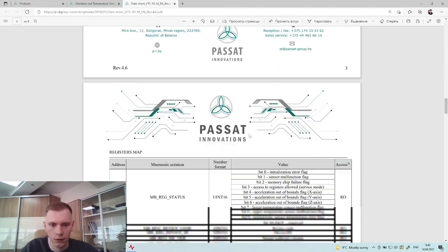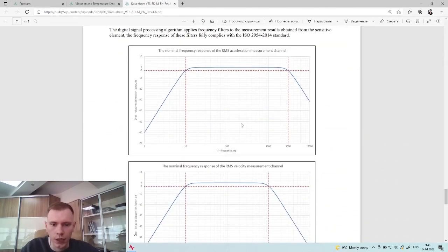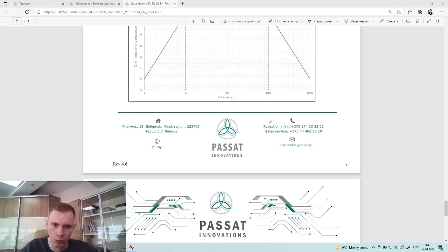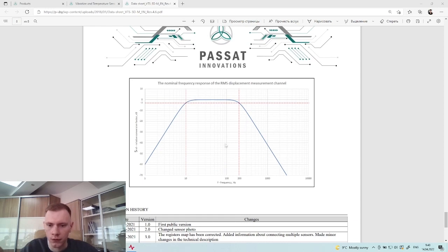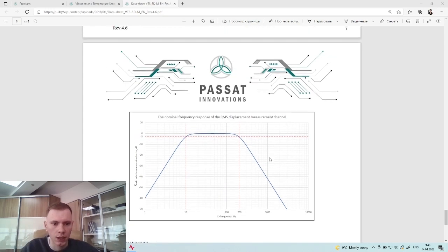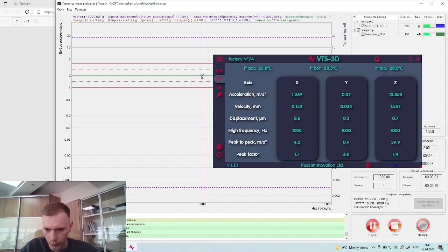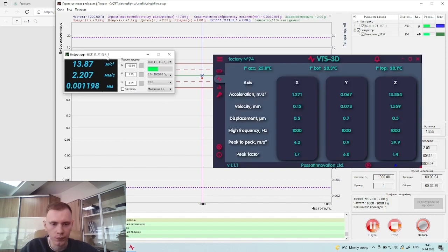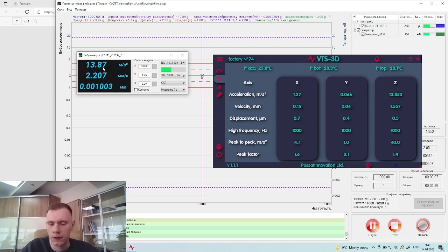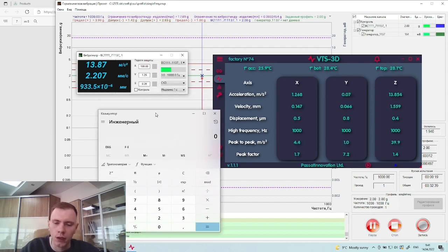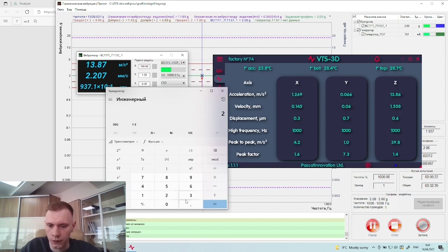At 1 kilohertz, we don't have to see any changes for acceleration, but for velocity we will have minus 3 decibels, and for displacement we will have like minus 40 decibels. So let's see. And it says that our acceleration measurements are very accurate and very close to our feedback sensor, but velocity measurement has some difference. So let's recalculate it.